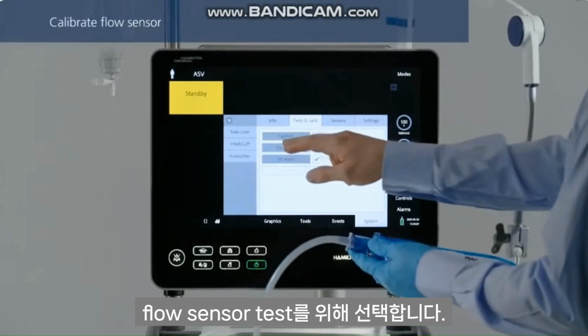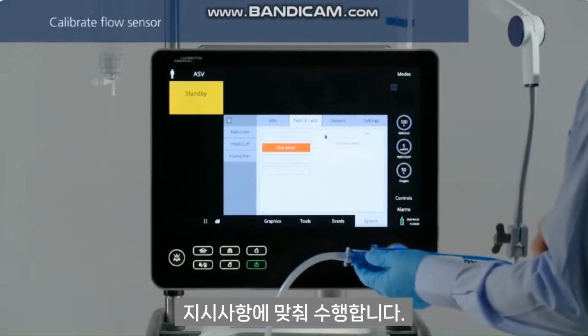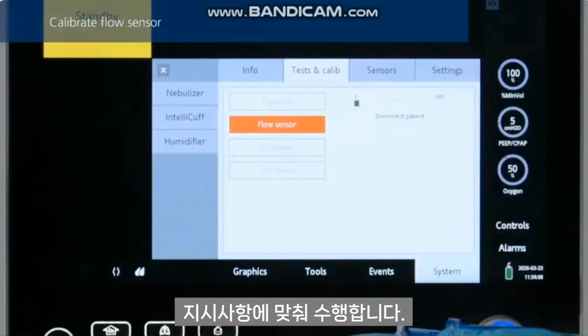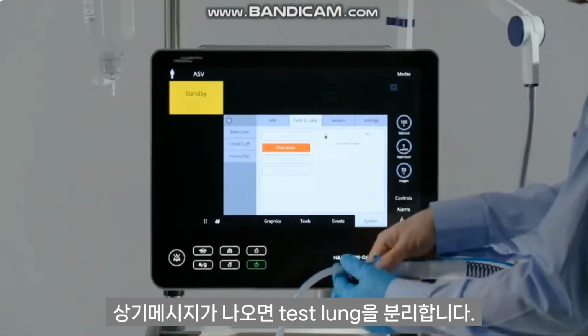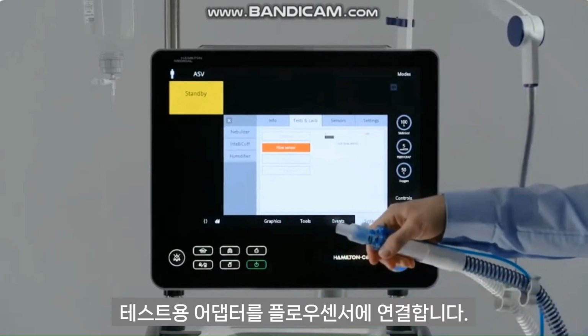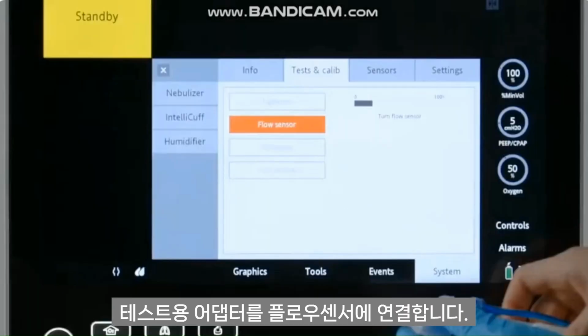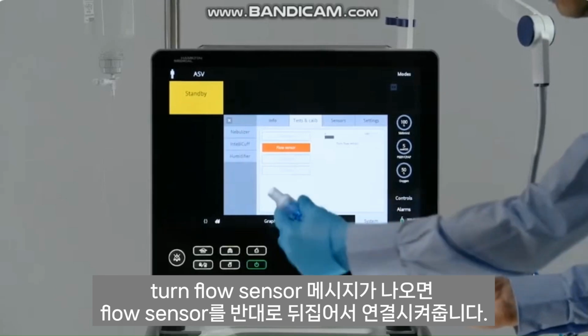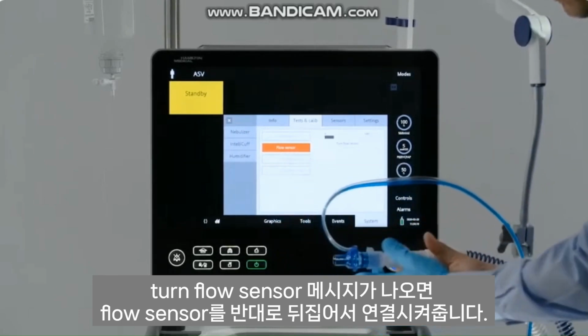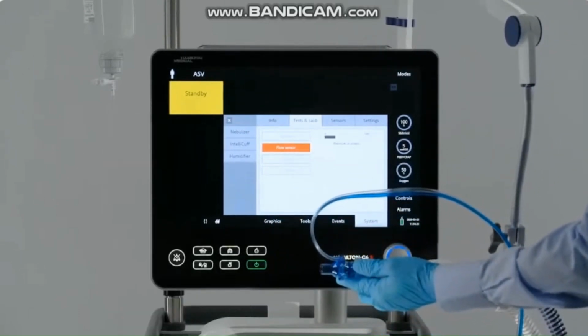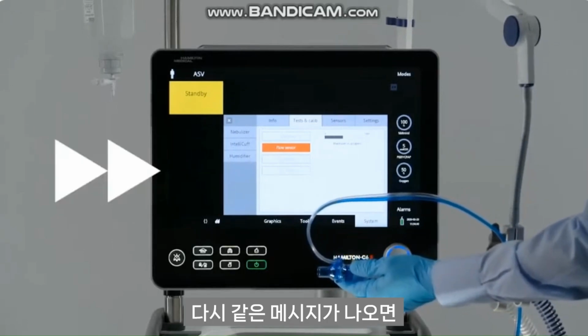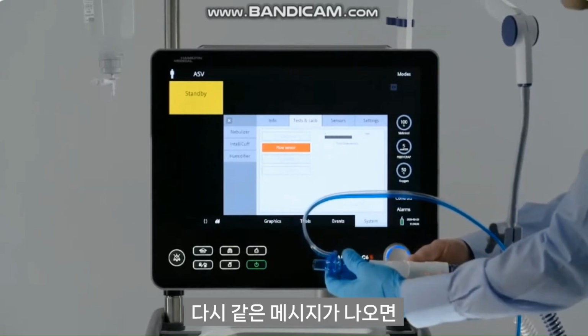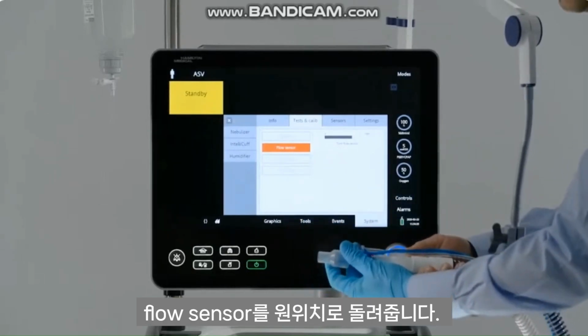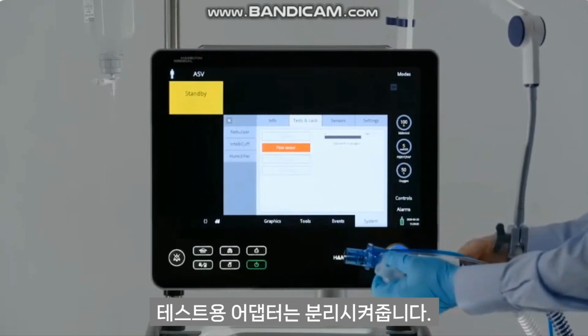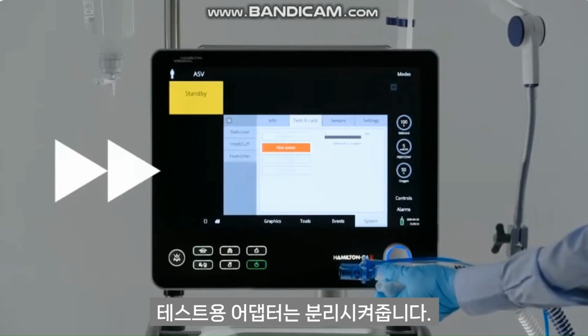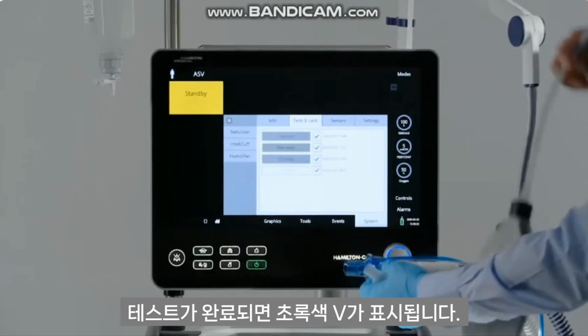To calibrate the flow sensor, select the desired operation, then follow the instructions from the ventilator. When the Disconnect patient message appears, disconnect the test lung and attach the adapter to the flow sensor. When the message Turn the flow sensor appears, flip the flow sensor. Wait. And then flip the flow sensor back to its starting position. Disconnect the adapter from the flow sensor. When calibration has been completed successfully, a green check mark will appear.